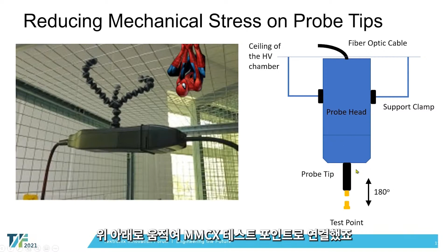The other way that I've seen that done is using gravity as your friend, where in the picture on the right, I've drawn a diagram of what one customer has done. They've taken the probe, fed it through the high voltage chamber, and hung it through some support clamps up on the probe head, and then they can move the probe head and probe tip vertically up and down into the MMCX test point. But it ensures that there's no strain horizontally on the probe tip or on the connection point itself. So that's really important to keep in mind, and those are some of the clever ways I've seen mechanical stress reduced on the probe tips themselves.